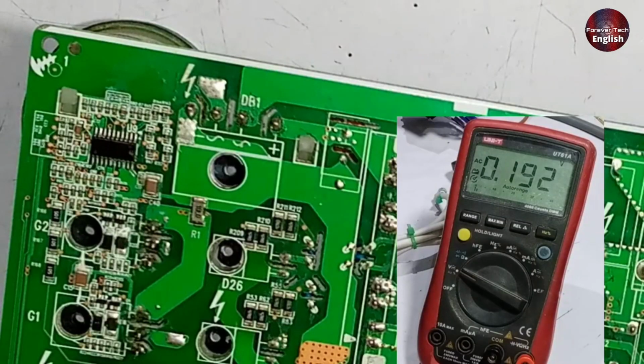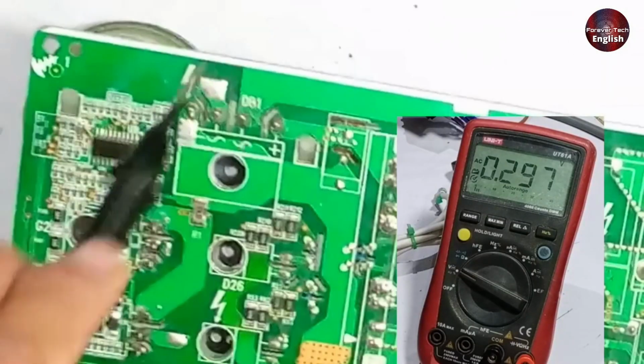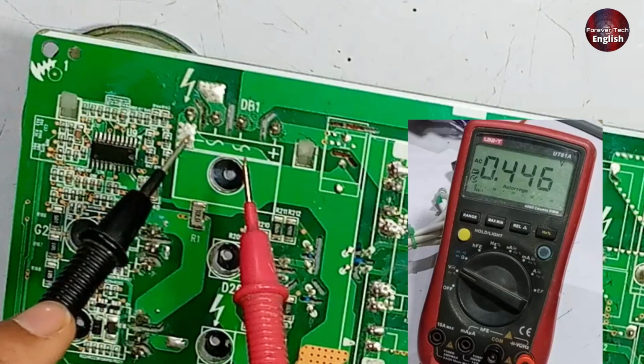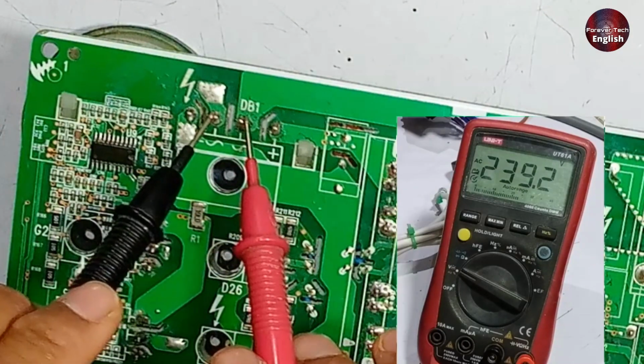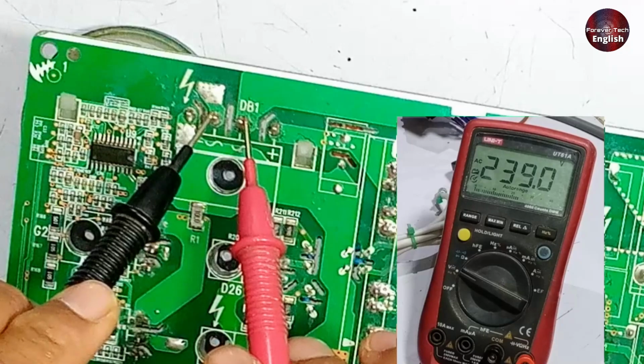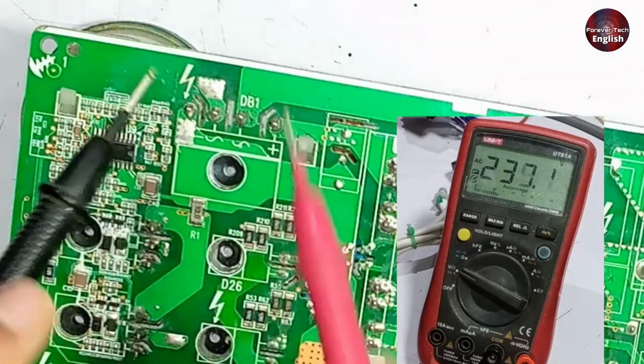After this, the system moves to the rectification stage. At this point, the inner terminals should show 230 volts. Here, we are reading 239 volts, which indicates that everything is fine up to this stage.